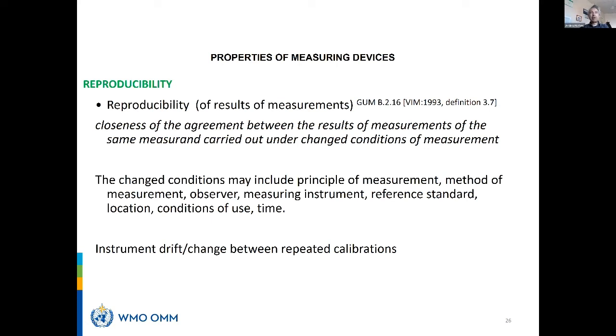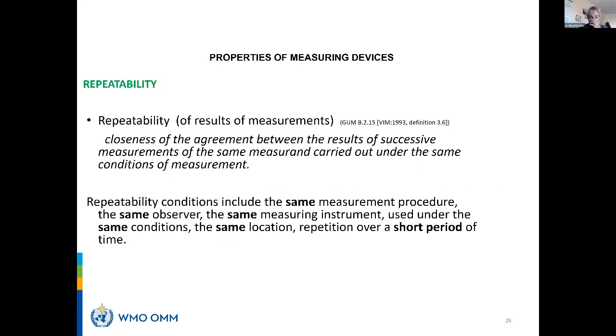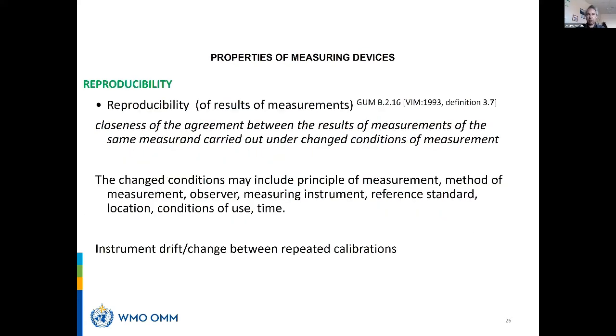Or some other change occurred - say I measured this ice point last week and got a certain resistance, then I do the measurement again a week later, not at the same moment. Repeatability is repetition over a short period of time - now and a minute later. Reproducibility is a week later - something changed.